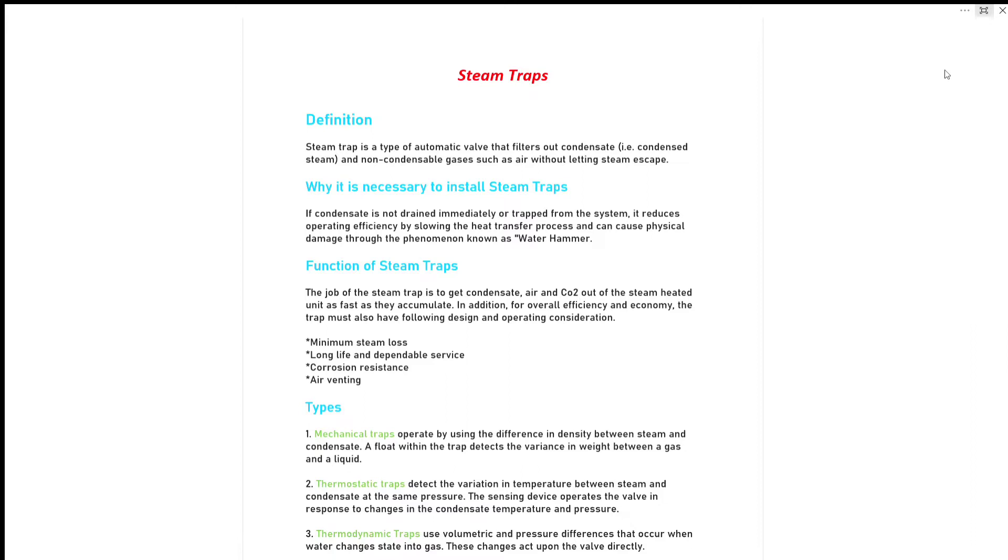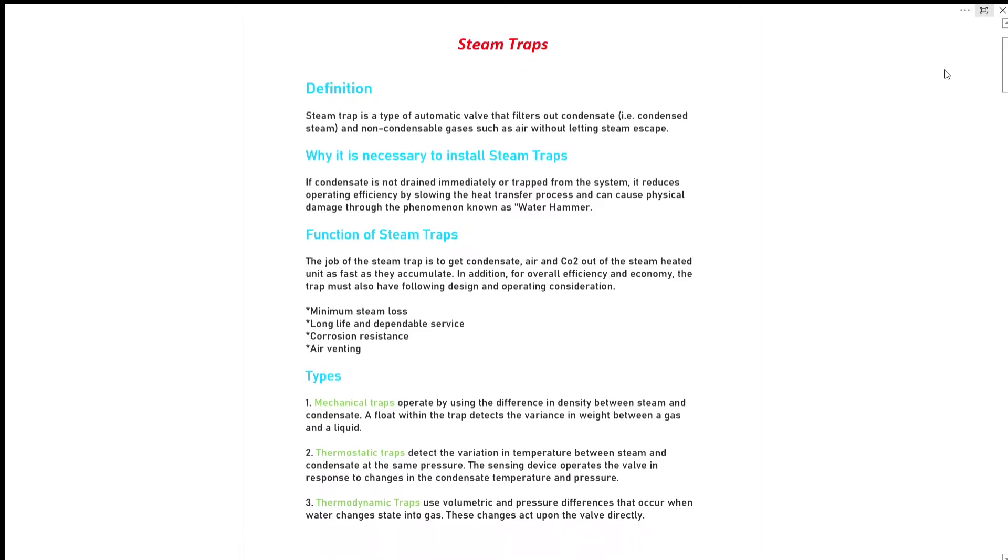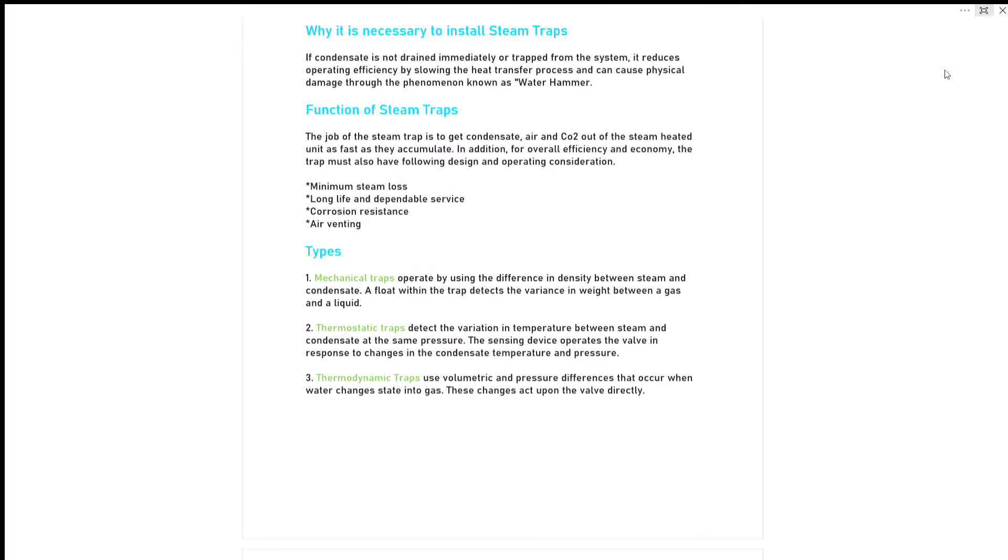That is: minimum steam loss, long life and dependable service, corrosion resistance and air venting. There are generally three types of steam traps: mechanical, thermostatic and thermodynamic. Mechanical steam trap operates by using difference in density between steam and condensate. A float within the trap detects the variance in weight between a gas and a liquid.